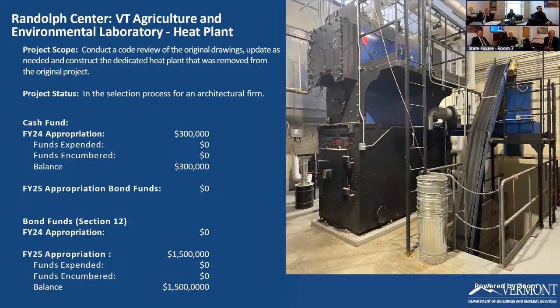The other thing is, during the summer, the college doesn't use their boilers. They will shut them off. So they leave one running now to provide the steam to this building. But because that building is so oversized, the boiler short cycles. So basically it just turns on, warms up just a little bit, and has to shut off. It's constantly doing that. Instead of being the right size, boilers like to come on and run. So that short cycling is hurting their equipment and they're going to end up having to do more repairs on it because of that.